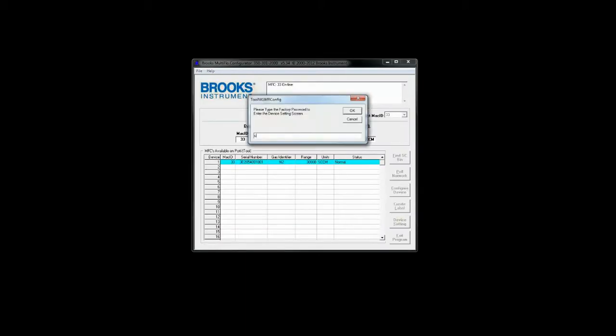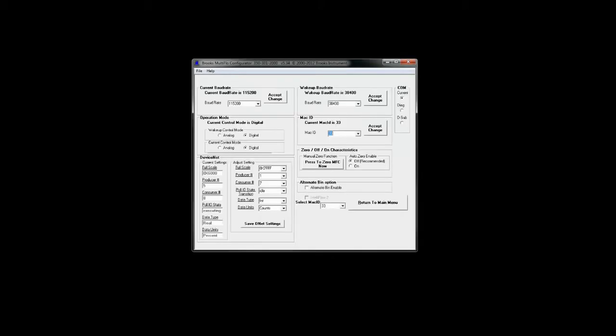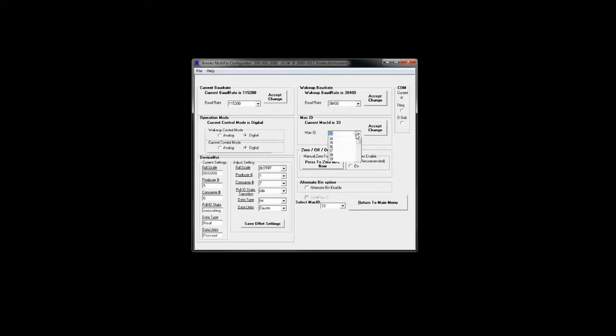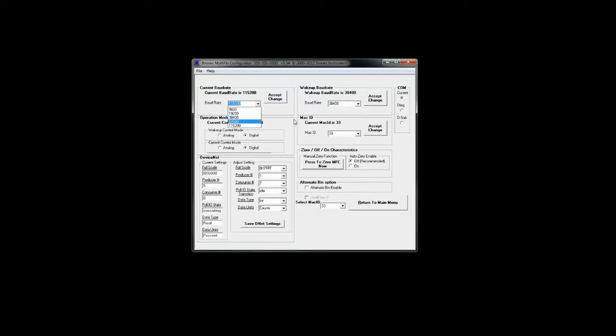In the device setting menu the password is CEL123. You can change the wake-up state of the device, which is the device setting at power-up. You can switch between analog and digital mode, change the MAC ID if you have multiple devices on the same com port that you need to differentiate, set the current and wake-up baud rate, zero the MFC, and change DeviceNet settings.